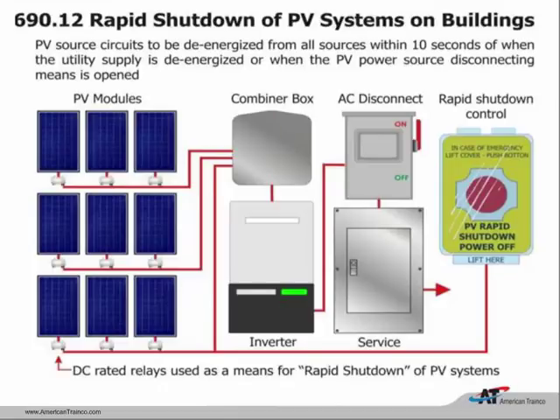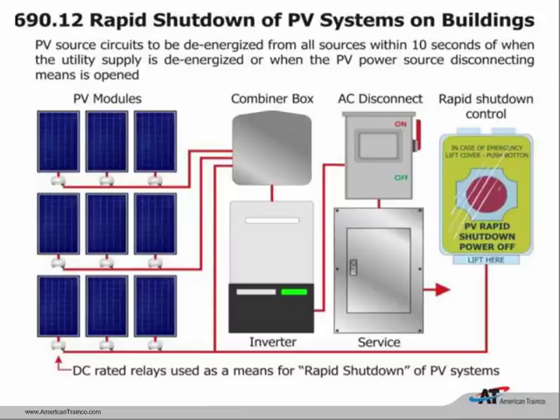Article 690 covers photovoltaic systems, which are becoming extremely prevalent. There is now a requirement to de-energize the PV system within 10 seconds in case of an emergency—this is really for firefighters. If firefighters need to de-energize a facility, a rapid shutdown button must be located near the service where they would be working. Shutting off the service does not de-energize the array system. Using DC relays, hitting that button de-energizes the relays—there will still be some power up on the roof, but the area where the firefighters are working will be safe.